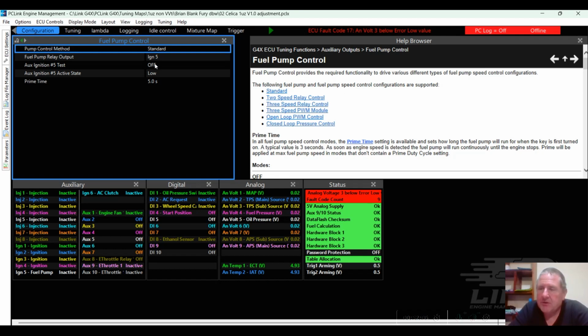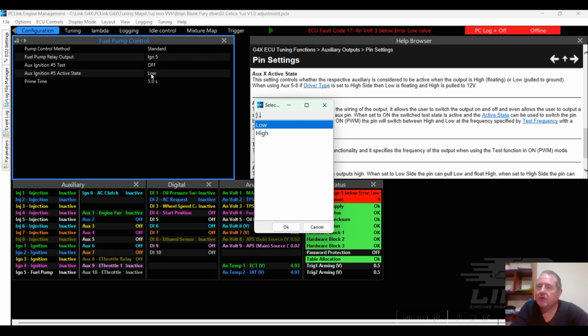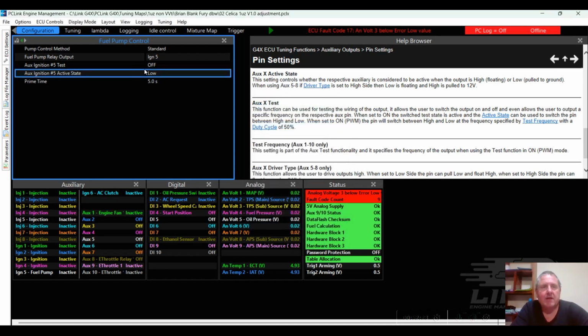If you want to test the output, you use this on, off, and low. That means it's going to drive when it's on. The active state is going to be low. It's going to be an earth output, not a 12 volt. If you go to high, it will output a 12 volt. It isn't available on all outputs, and then you can test it. 5 seconds of prime is a lot of priming, but that's your own choice of where you want to put that. So low, it's going to drive to ground.